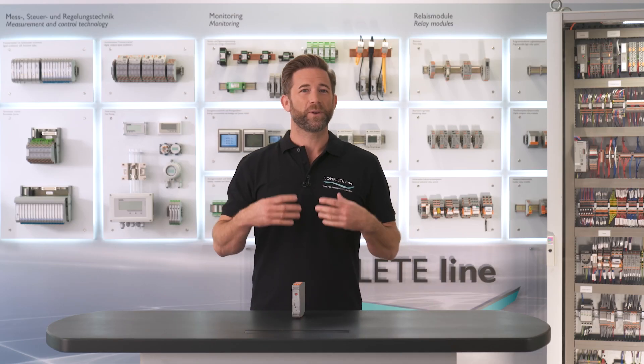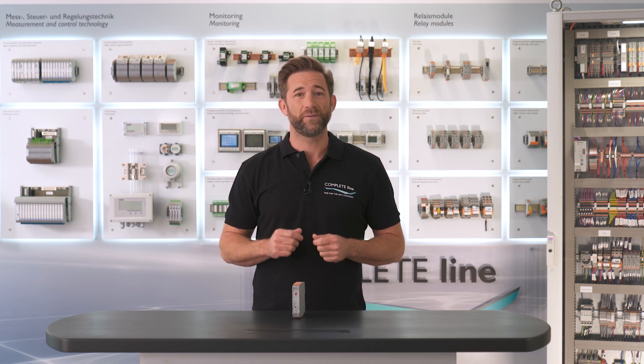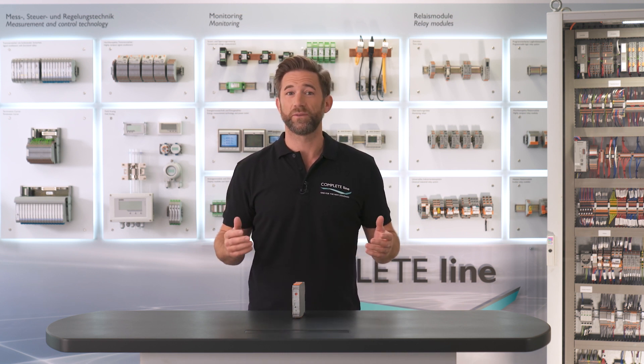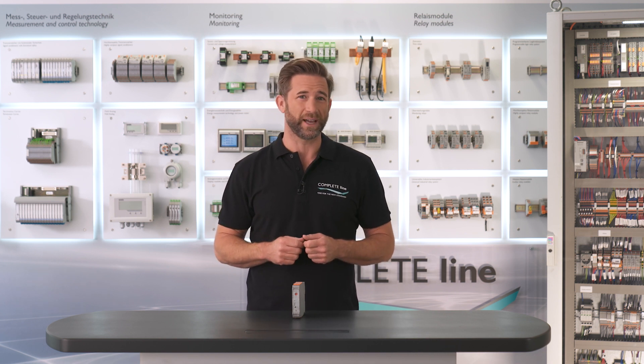This enables gentle switching and considerably reduces the load on the relay contacts. Compared with conventional solutions for motor switching, this offers several unique advantages. First of all, the low-wear switching ensures 10 times longer service life.